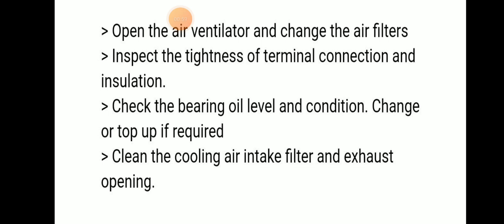Then we have to inspect the tightness of the terminal connections and their insulation. We have to check the bearing oil level, whether it is good or not. If its quality is bad, we have to change it, or if the level is very low, we can top up if required, depending upon the condition.